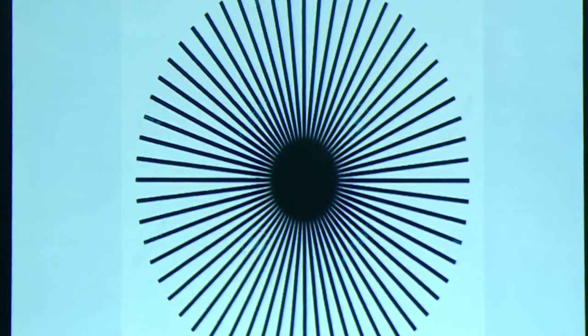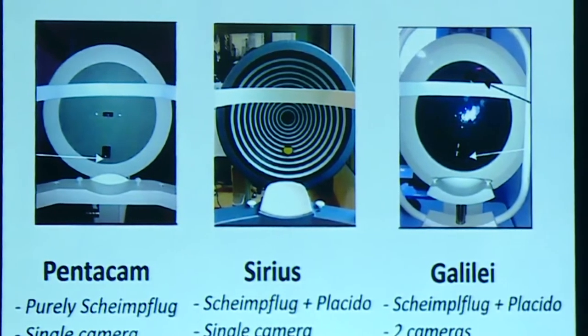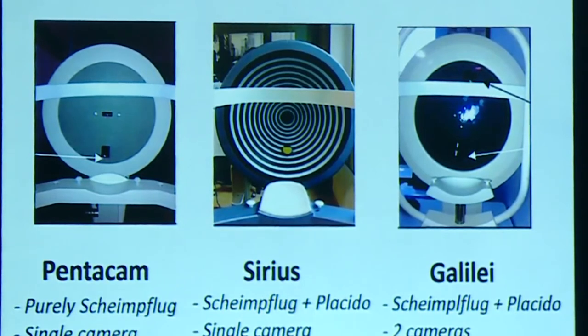In Scheimpflug devices, slits are projected so that the maximum data points are at the central 2–3 mm, because as corneal surgeons we know patients see 90% of the time through the central 2 mm. More data points in the central cornea means better reproducibility and accuracy. In Scheimpflug devices we have Pentacam, Sirius, and Galilei. Pentacam is a purely Scheimpflug device, whereas Sirius and Galilei have also incorporated a Placido. Galilei features two Scheimpflug cameras along with a Placido camera.